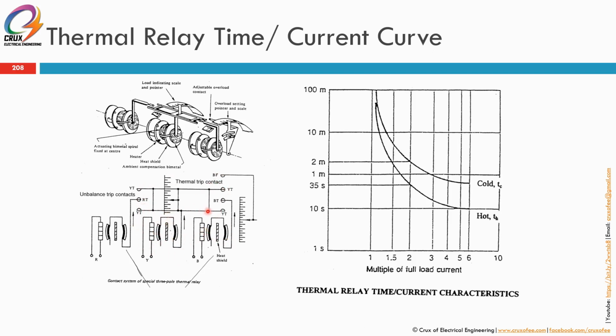Okay. So as you can see here, there's a cold curve and the hot curve. So normally during starting, we refer the starting and the tripping time to the cold curve. Once the motor has run and stabilized its temperature, it will trip based on the hot curve, the temperature time current curve.